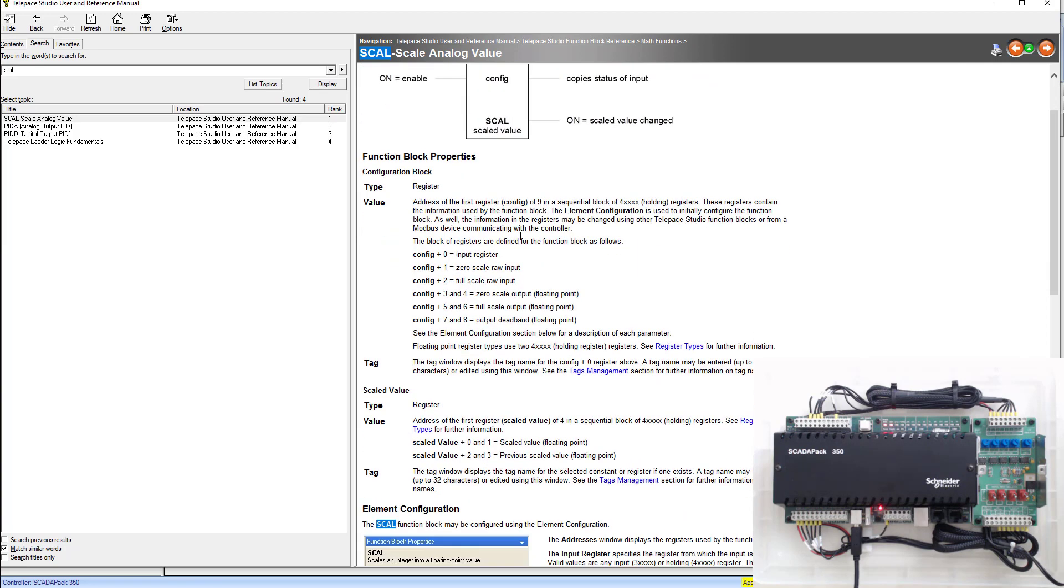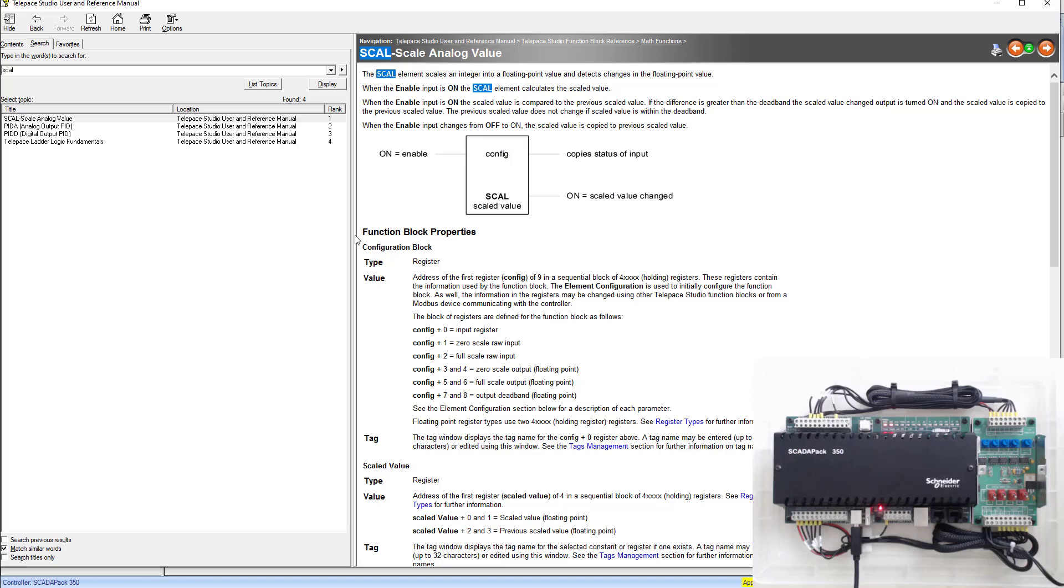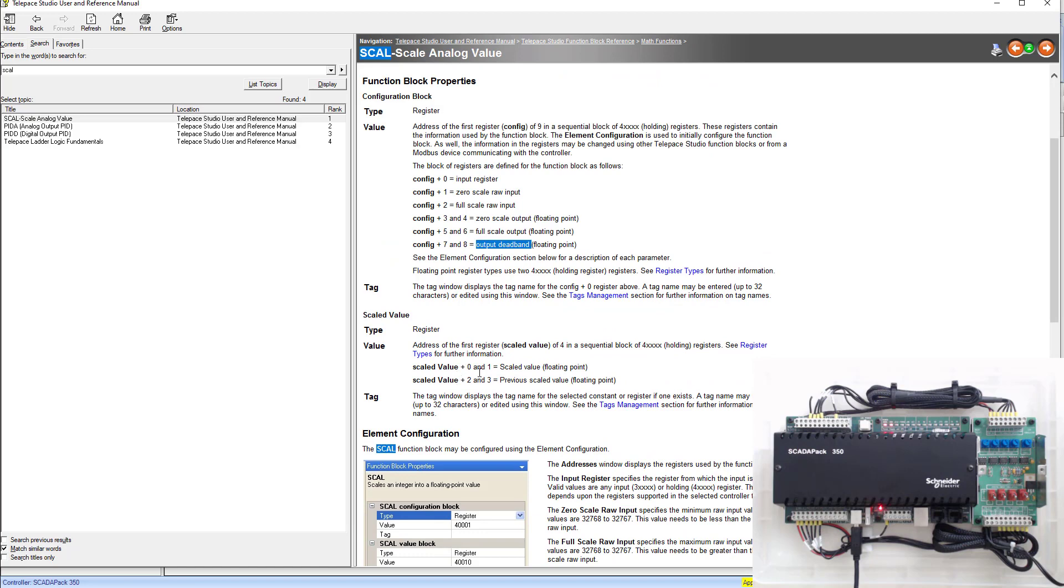In your scale block, it'll tell you that your configuration register will start here. The first register will be the input register. The next register will be the zero scale raw, then full scale raw, zero scale output, full scale output, output deadband, as well as your scaled value output and your previous scaled value output.